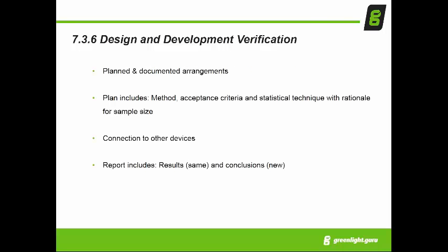So design and development verification needs to be planned, it needs to be documented, you need to have test methods and protocols. All of these things need to be established ahead of time. Yes, these are practices that many of you probably have in place. They were not always explicitly defined in ISO 13485. So that's some of the areas as you get into what's changed about ISO 13485. In some respects, the practices that have been accepted and in place at many companies were basically mimicking these changes. ISO 13485:2016 in some respects is a catch-up.